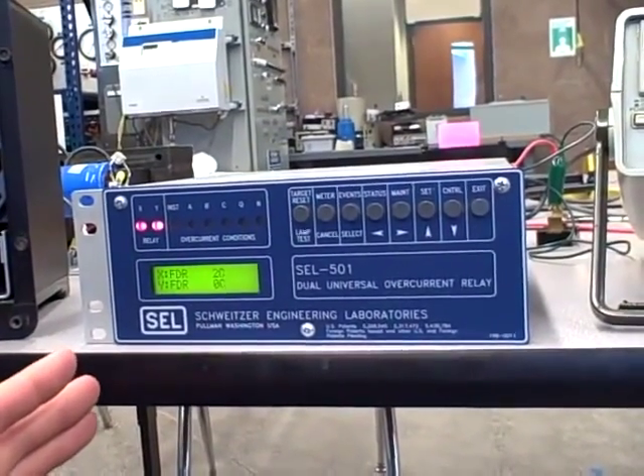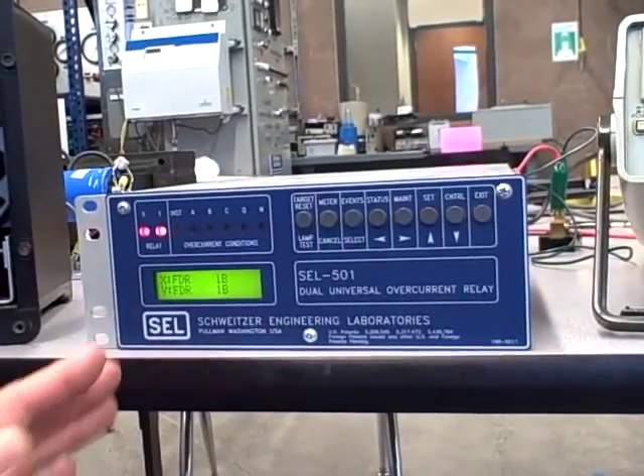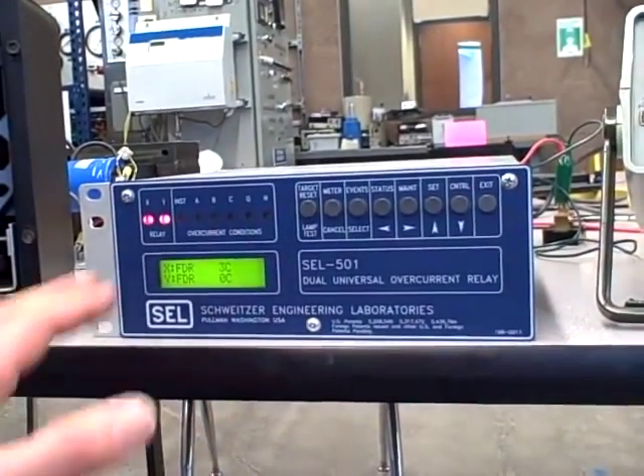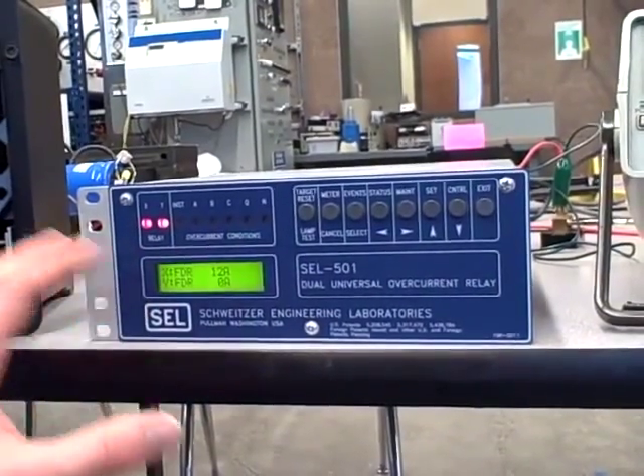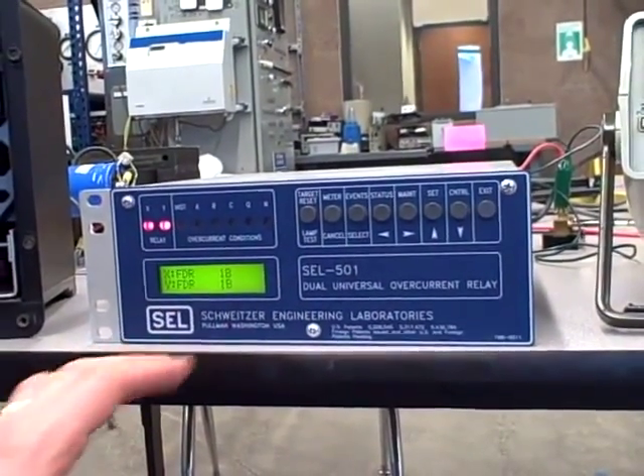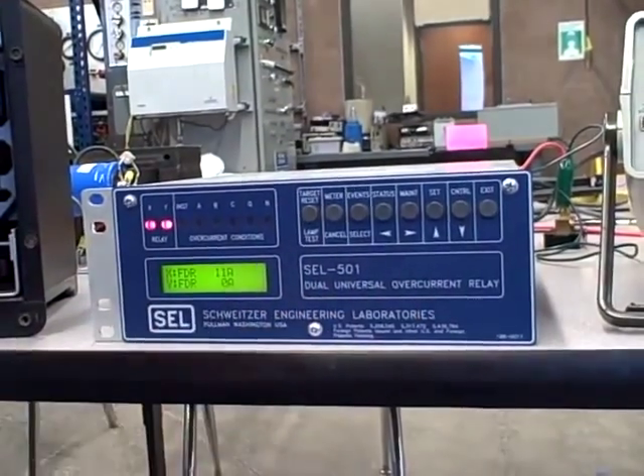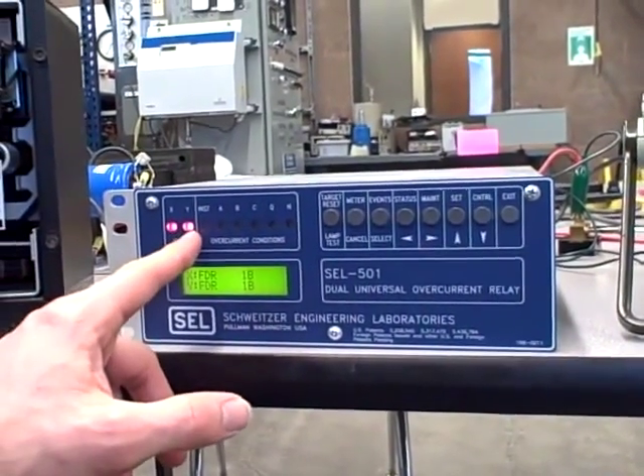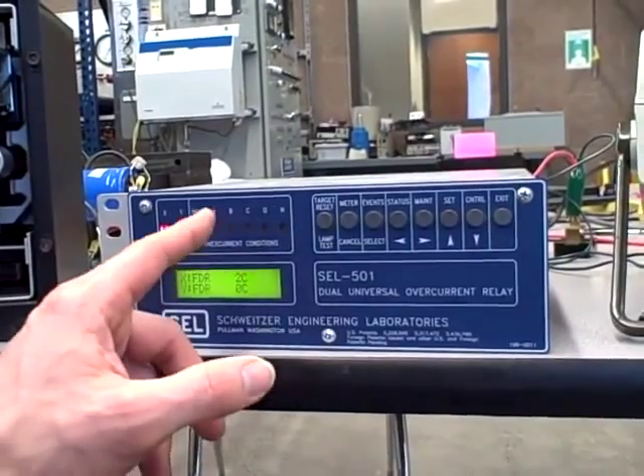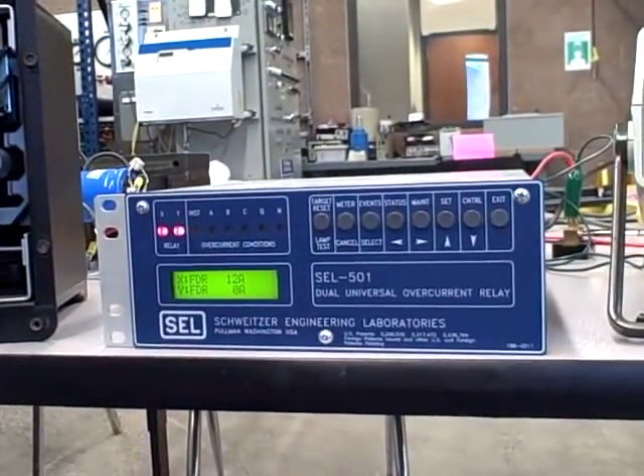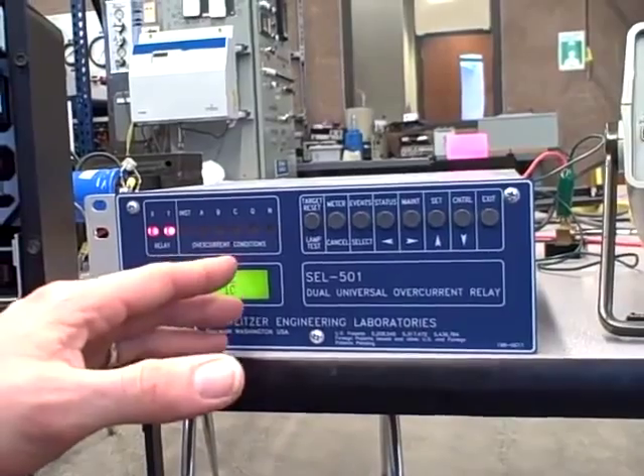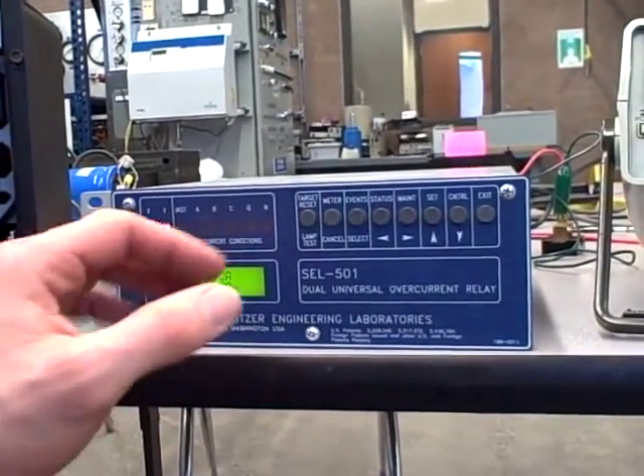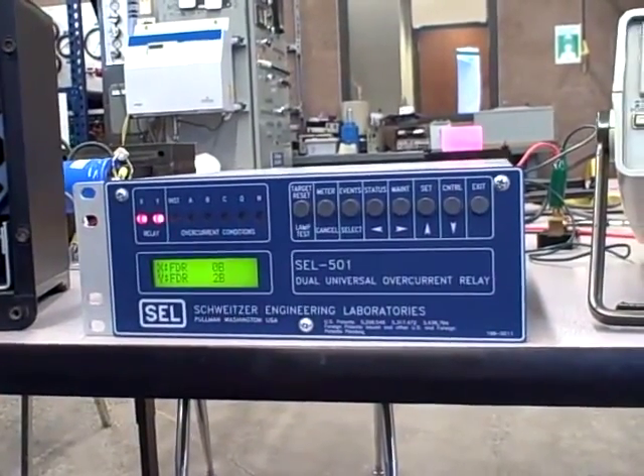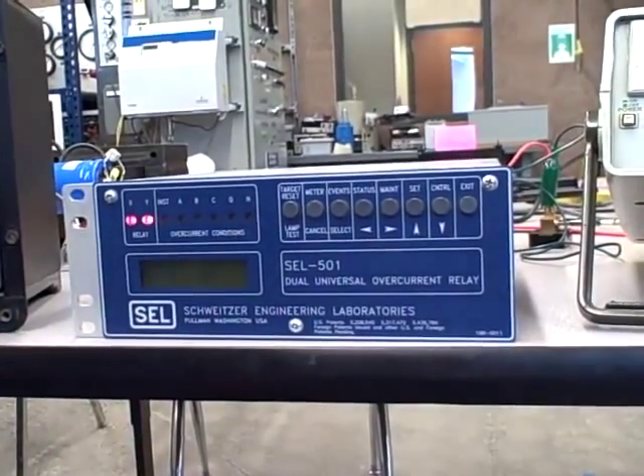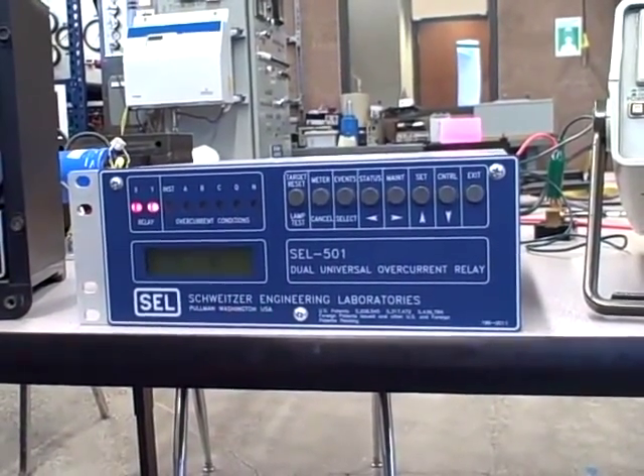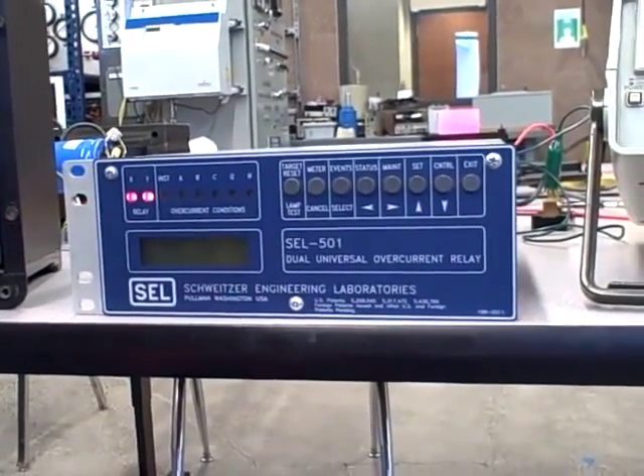So in this case, we've got a relay that is not only monitoring 3 phases, but also doing it on 2 separate relay functions. So it's actually 2 relays built into one unit, which is why they call it a dual universal overcurrent relay. Relay X and Relay Y, and each one of those has 3 current inputs, phase A, phase B, and phase C. It can also detect reverse sequence current and neutral current based on those 3 measurements. So it's a lot more capable unit than the single phase electromechanical we looked at before, but we're going to test it on 1 phase alone just to show you how it works.